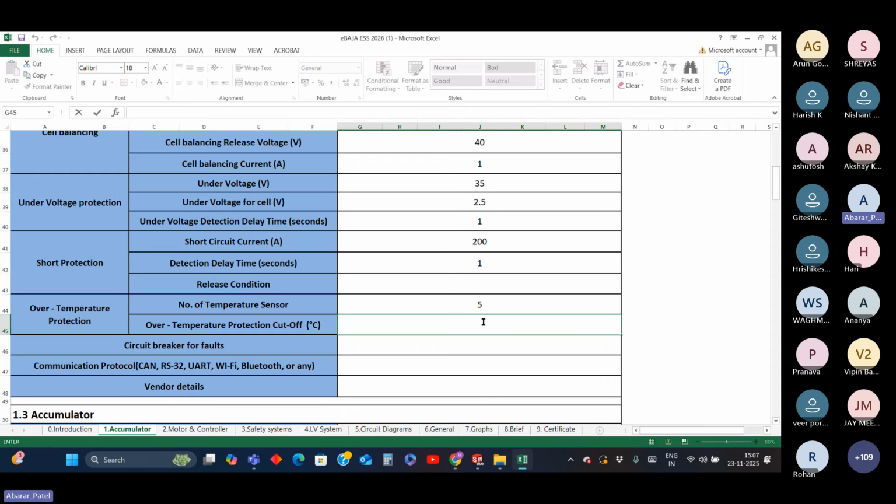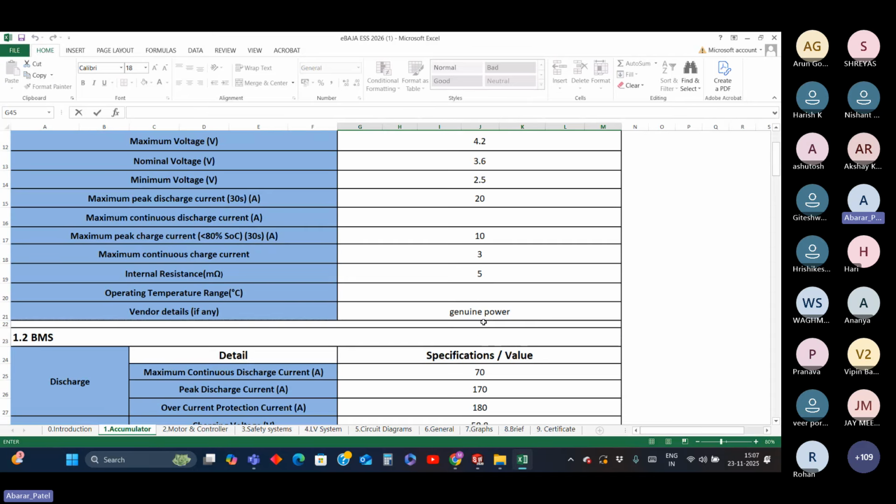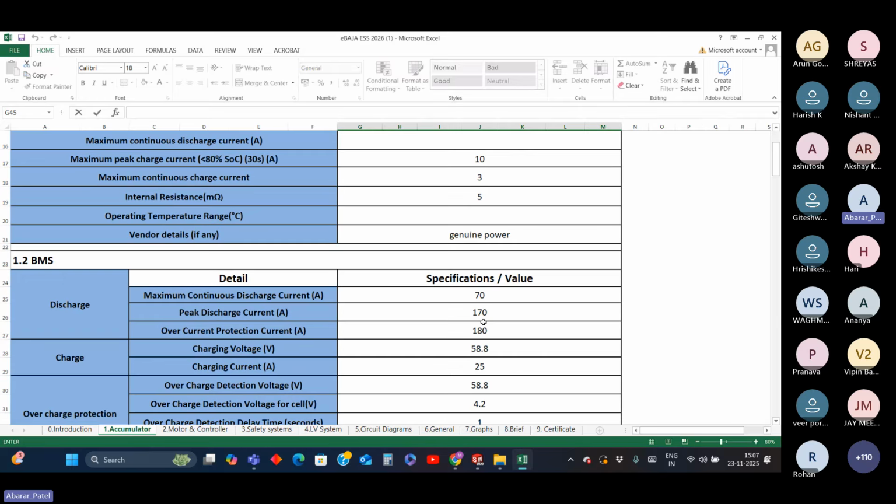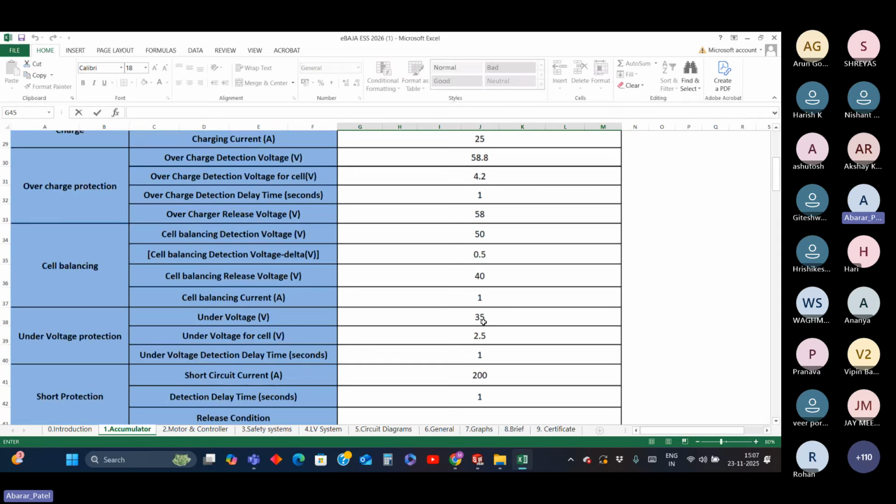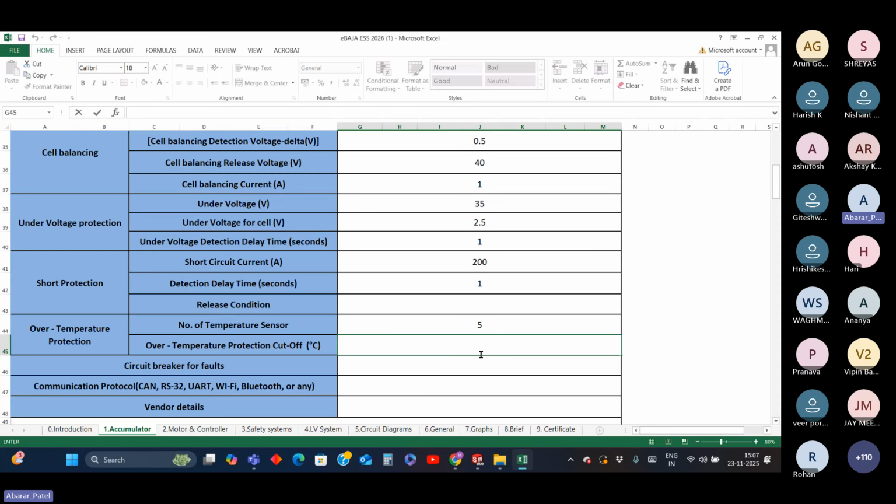And what is the over-temperature protection of your limits? Based on the operating condition of my cell, as I told, up to 60 degrees Celsius my cells can perform within the safe zone. So I will ensure to keep my protection limits well beneath these limits. Let's say in my case it is 55.